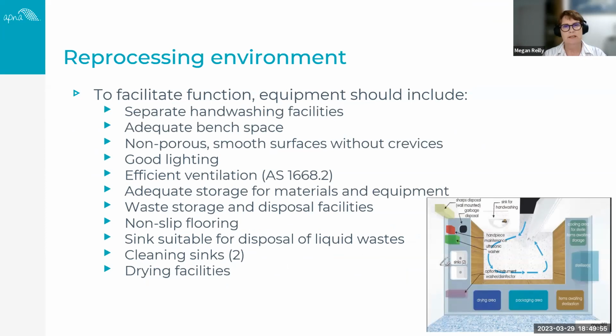So separate hand washing facilities, and I certainly understand that that can be a challenge for some environments. We shouldn't be using the cleaning sinks to perform hand washing. You need adequate bench space. You need surfaces that aren't porous, that are smooth and without crevices. You need good lighting. So that's under bench lighting, flush ceiling lighting, and some practices have an illuminated magnifying lamp light, because you need that to be able to inspect your instruments after they've been processed. So efficient ventilation, which is in accordance with the Australian Standard 1668.2. So that allows for the correct flow as well through your reprocessing environment.